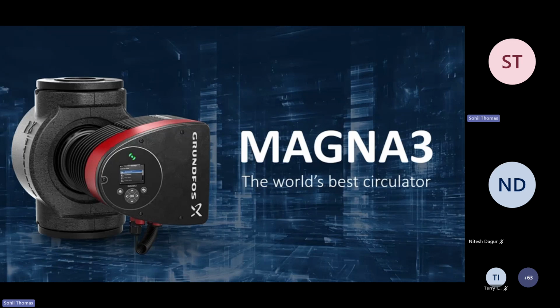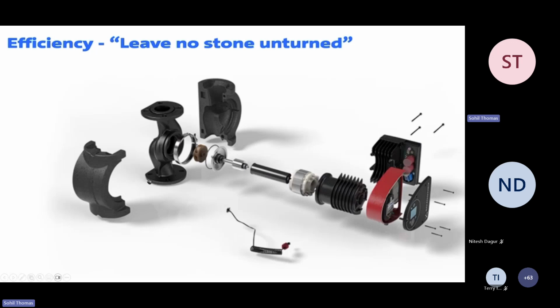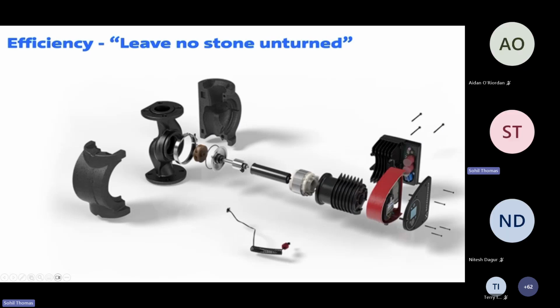So this is the pump that makes it possible to go with the distributed pumping concept, which is the smartest circulator that's available in the market. This is an ECM circulator. It uses a delta P and a temperature sensor that makes it highly efficient. And this is also a wet rotor circulator, meaning we allow some fluid to go through the rotor can that you can see here to cool the top and lower bearings and to make sure that it becomes maintenance free throughout its entire life.